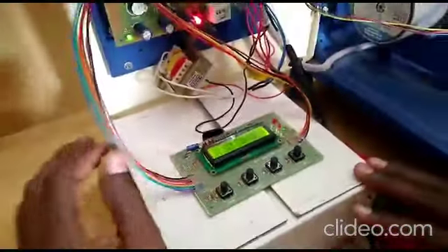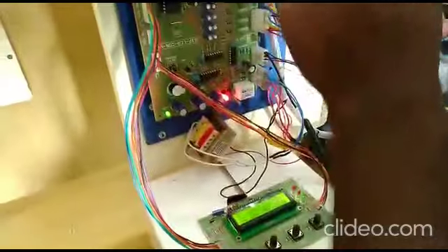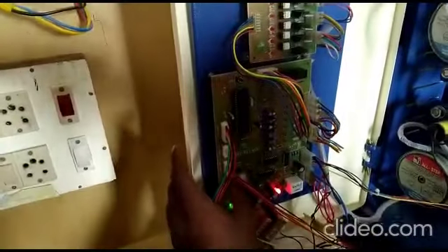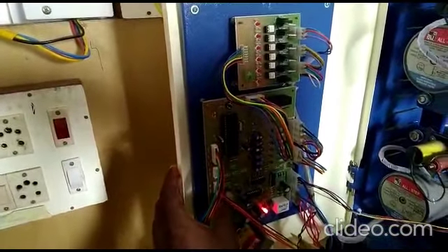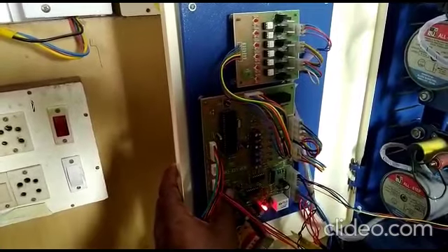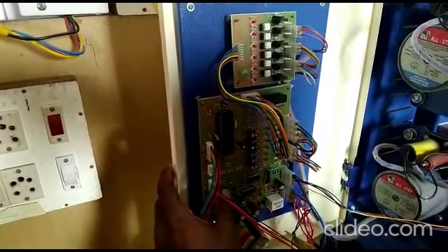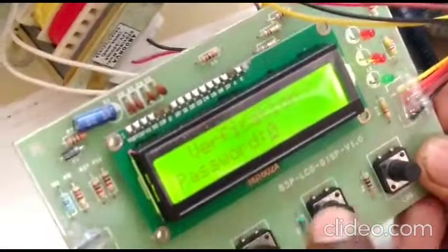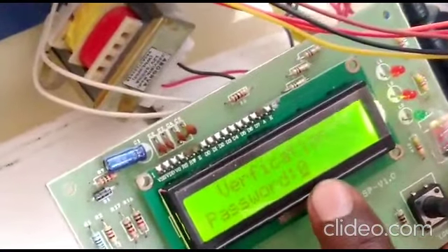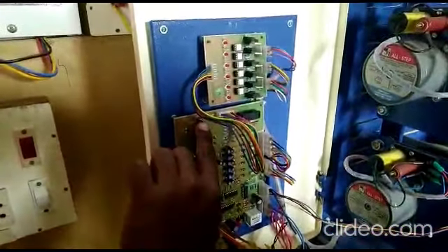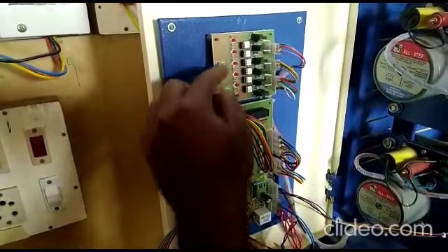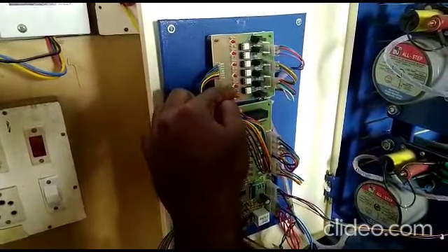Now we are going to test whether the triac is working or not. How to test the triac board? Just go to the auto or manual button and long press. The display will show the verification password. During the triac board testing, this value should compulsorily be 0. Now we press the test button. When we press the test button, these LEDs blink in some order.